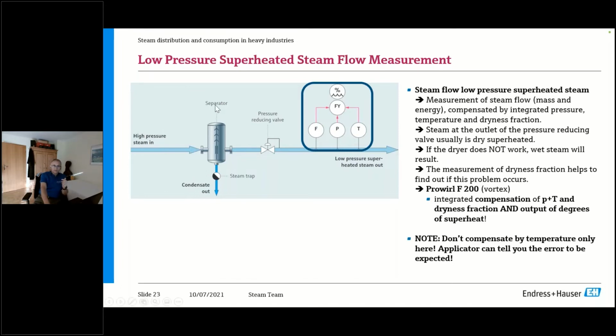Another problem is that those separators come with a certain specification. In theory, they may be good down to a steam quality, a steam dryness, of 95%. They really specify the amount of moisture they can take out of the system. But if you have more moisture coming, what's going to happen? You keep that in the system, and this is going to end up downstream. So you expect to have superheated steam, but in reality it's wet. Therefore, at that measuring point I clearly recommend measuring pressure, temperature, and the dryness fraction for compensation purposes. In these cases, this is very, very helpful.